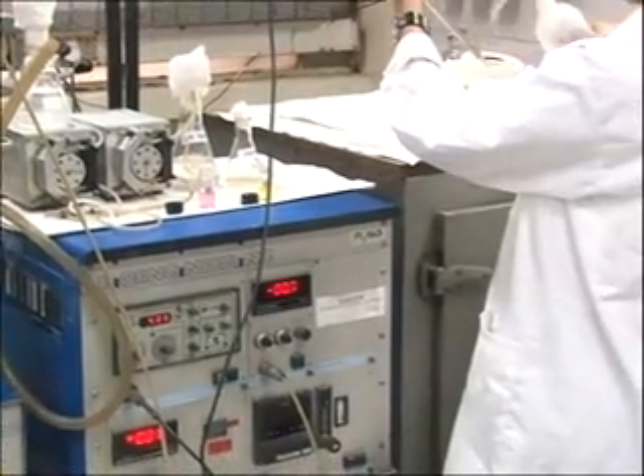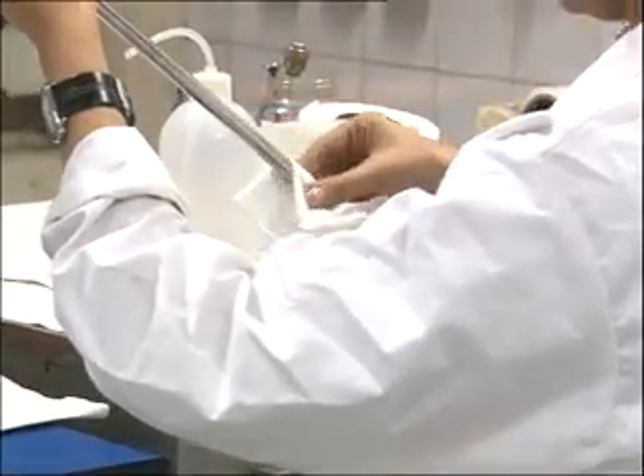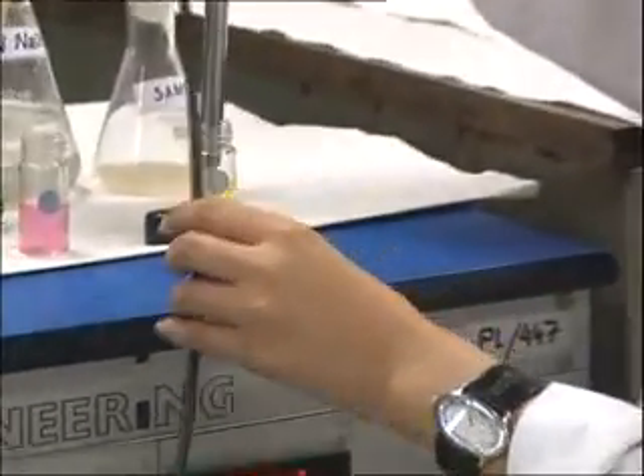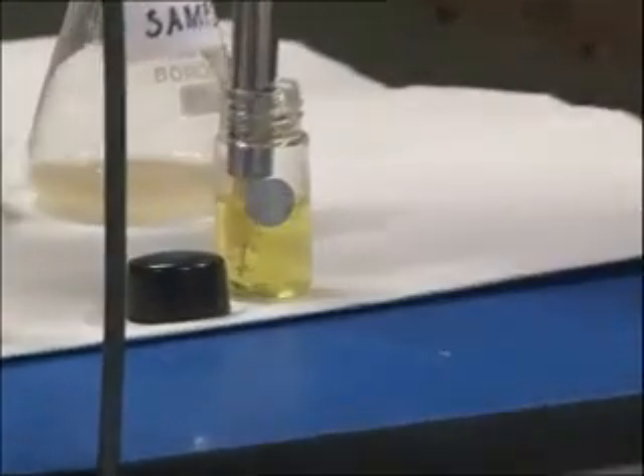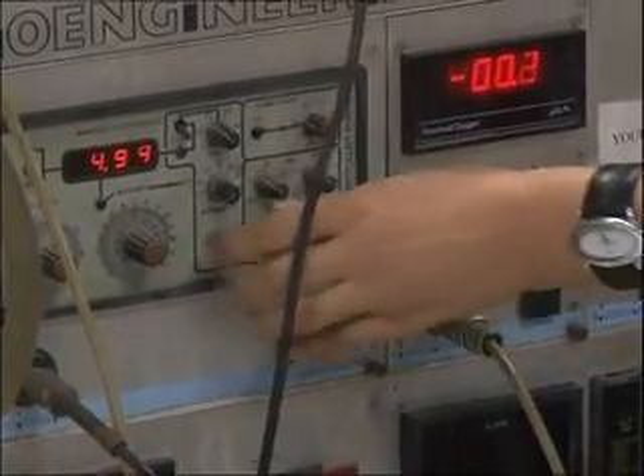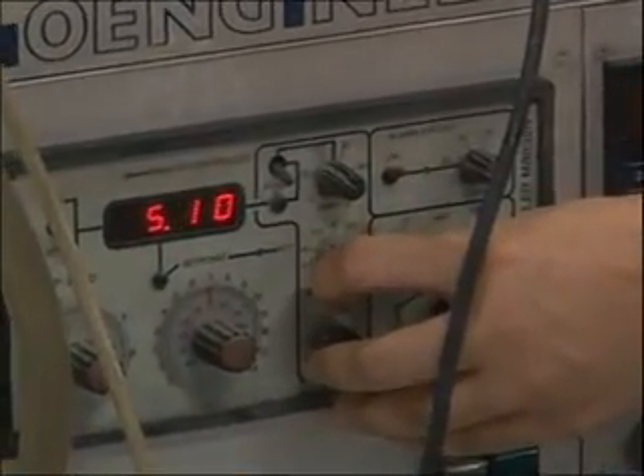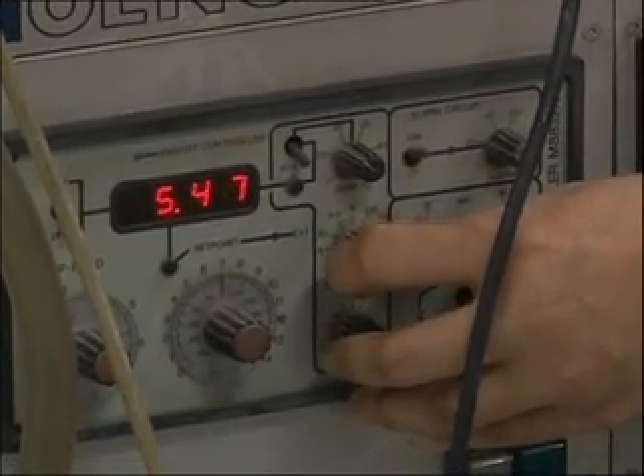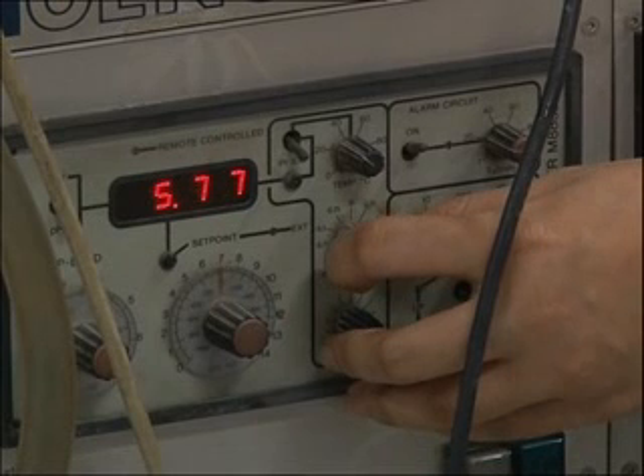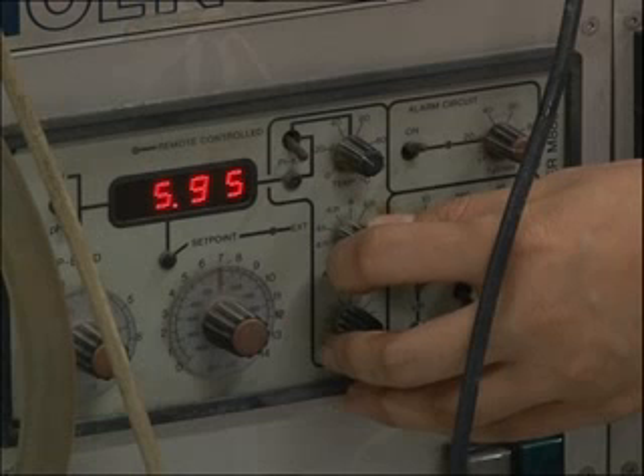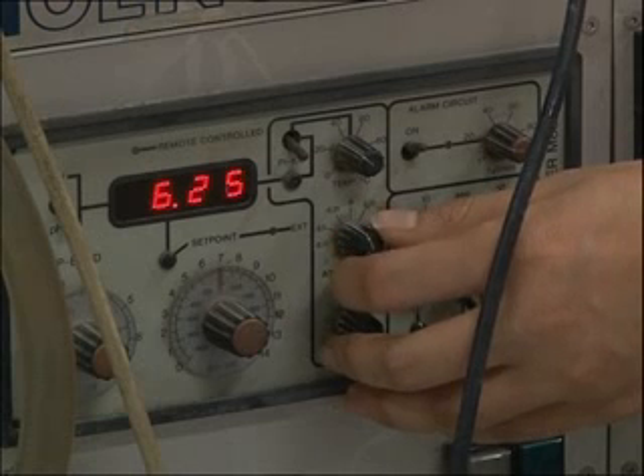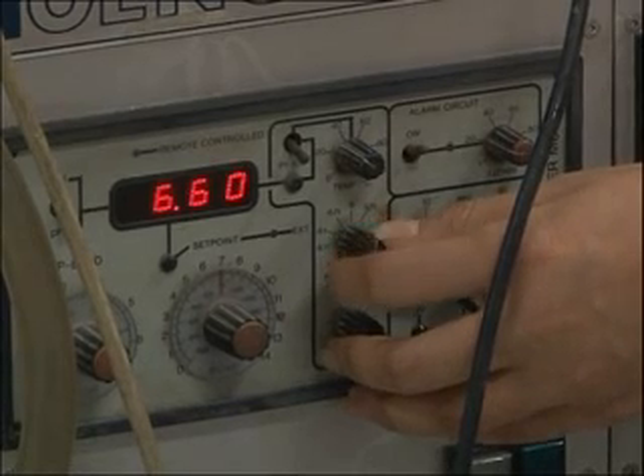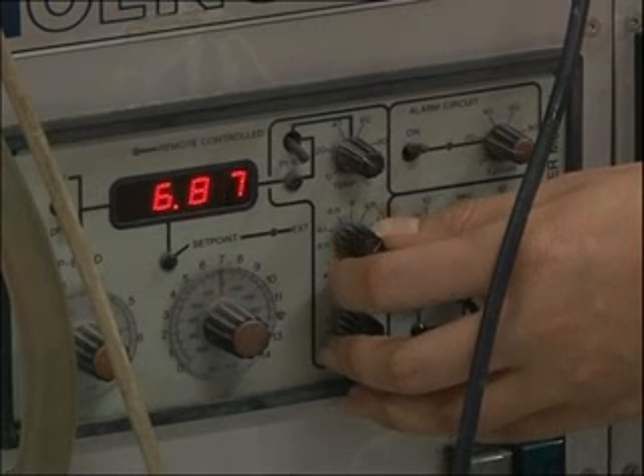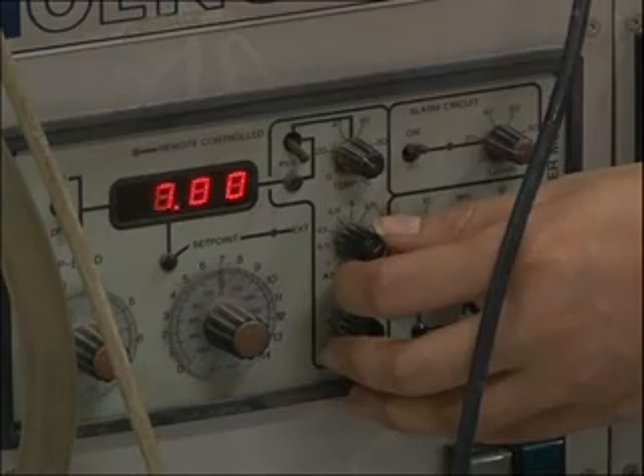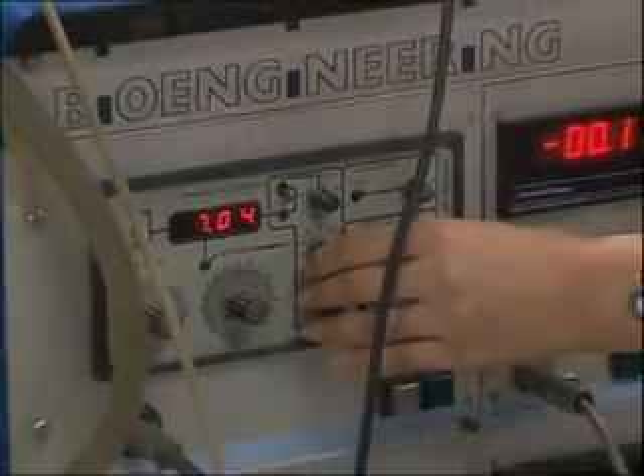The probe is washed, dried, and then put in another buffer, that is pH 7 buffer, as you see over here. The meter should read 7 over here. If the reading does not show 7, then we adjust it by the asymmetry knob potentiometer, as shown over here, and make it 7. Okay, now the probe is perfectly calibrated.